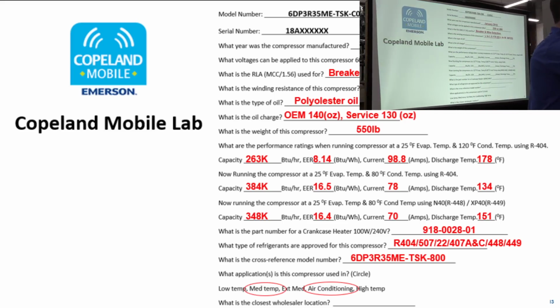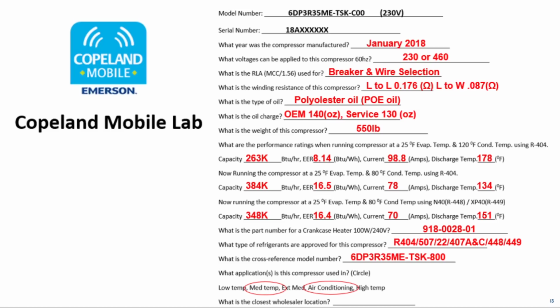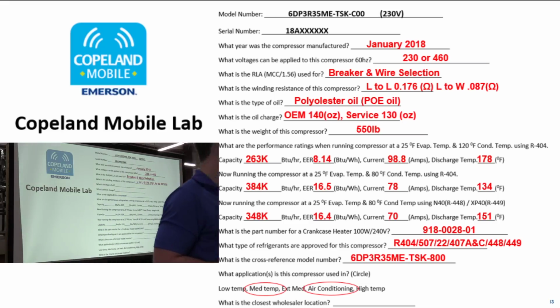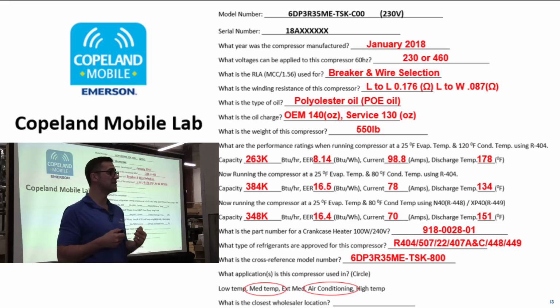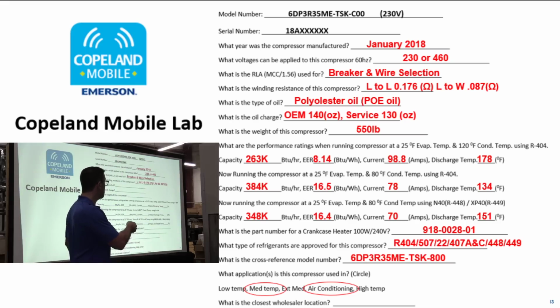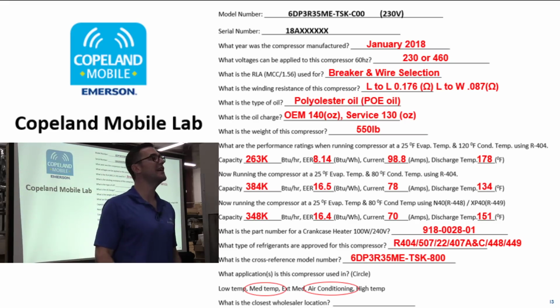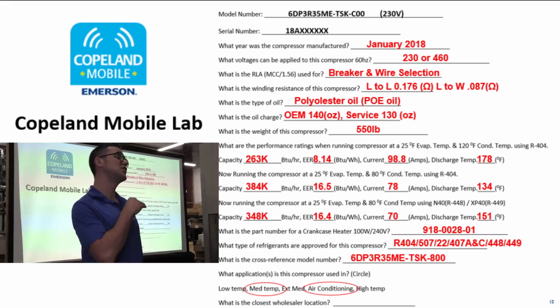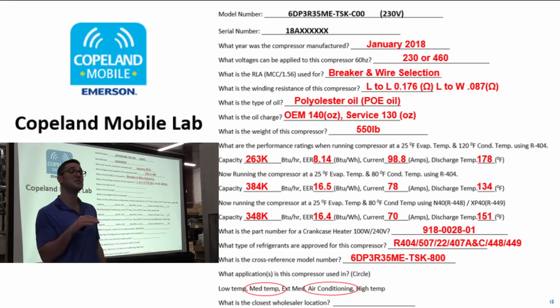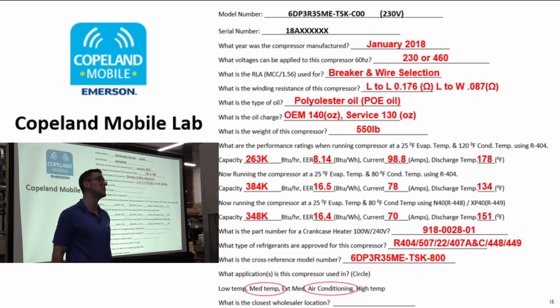What's your name, sir? Art. Art. So what does that mean, line to line now? What do you got to do? Check your, not your voltage, that's okay, your ohms. Your ohms, right? So you pull off your wires and it should be really close to 0.176. So at first I was like, oh, that can't be close. Oh, I checked so many compressors over the last couple of years, and they're pretty much bang on if they're a good compressor. So how valuable is that to you guys in the field, right?